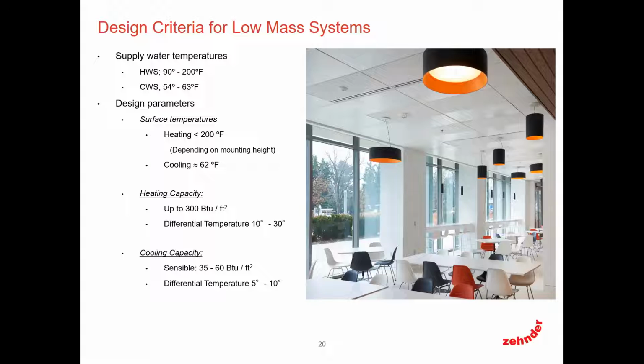One of the pitfalls that I've seen happen over and over again on schedules and drawings has been the initial selection being with either a closed ceiling or an open to structure capacity in cooling or heating mode, and then the design is switched to the opposite, and you don't get that same BTUs per square foot. So then you have to either add more square footage in, change some water temperatures, or change panel types to make sure that you're covering your load. So just something to be aware of when you're approaching the design. With regards to the panels, these are lightweight, fast reacting panels. So generally we design 1 to 2 degrees supply water temperature above your dew point to avoid condensation. I designed a lot of high mass systems, meaning in-slab PEX tubing.